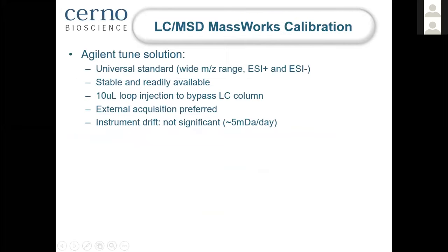In terms of the standard used for the LC-MSD, the Agilent tune solution is a very ideal standard. It has a wide m/z range. You can do it in both positive and negative mode. It's very stable and readily available inside the instruments. You can do a 10 microliter loop injection to bypass the LC column, because the tune solution is not the best suited for column separation. So loop injection bypassing the column is the best way to do it, and it can be very fast, 1 or 2 minutes. And you inject this as an external standard.